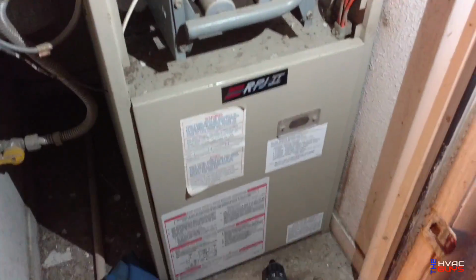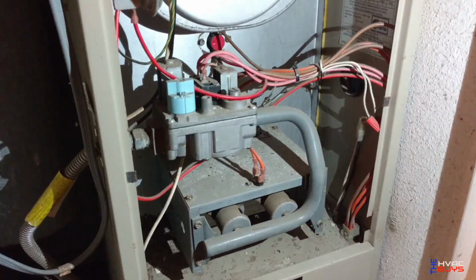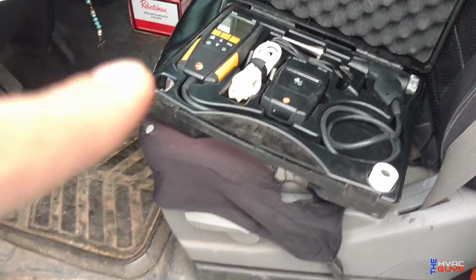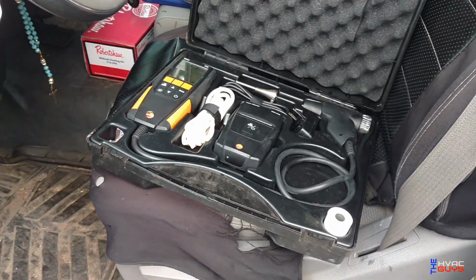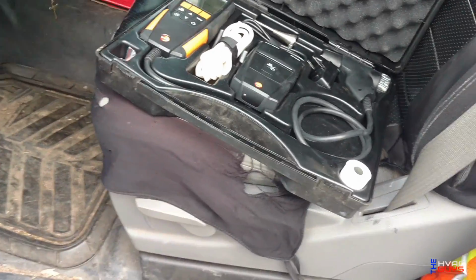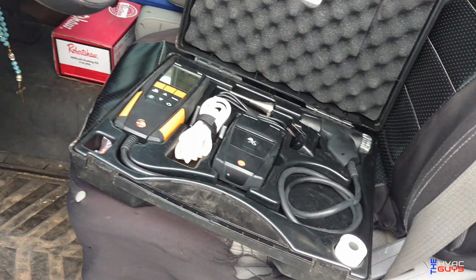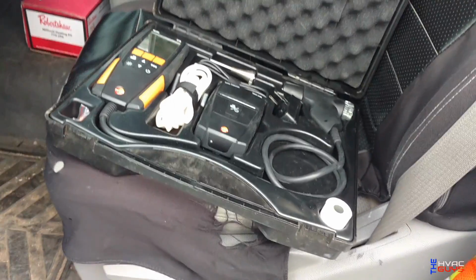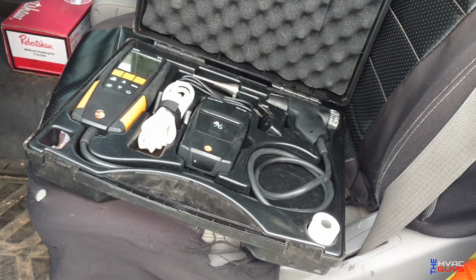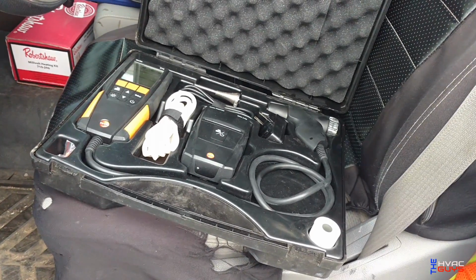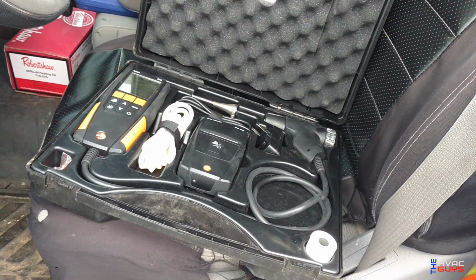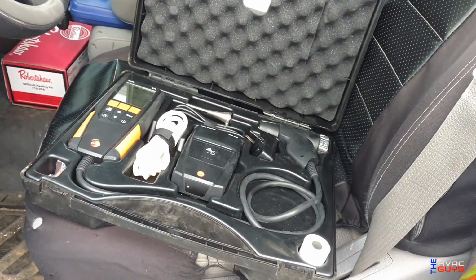Yeah, bring it, she got a little wavy right now. Whoa, hold on. This is why it's very important to have one of these combustion analyzers. So we turned that furnace on, and then I saw the flame. When it turned on, it was nice and blue. And then when the blower motor kicked on, it got wavy. So I was like, what the hell?